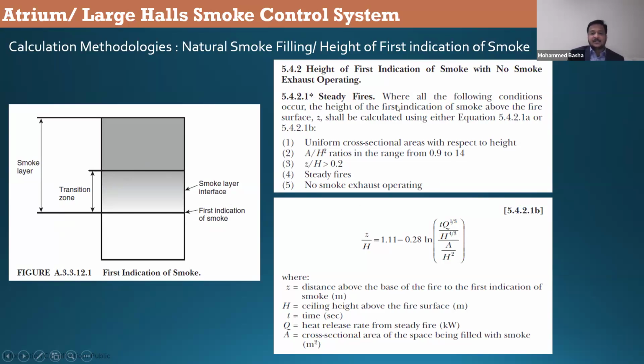Okay, when can we use this system? Where all the following conditions occur: the height of first indication of smoke above the fire surface, which is Z, as I have explained before, shall be calculated using either equation 2.1a or 2.1b. Why two? One is in SI units and one is in American units. So the conditions here are, this should be a uniform cross-section area with respect to height, I mean the smoke filling area, with A by H ratios in the range of 0.9 to 14.